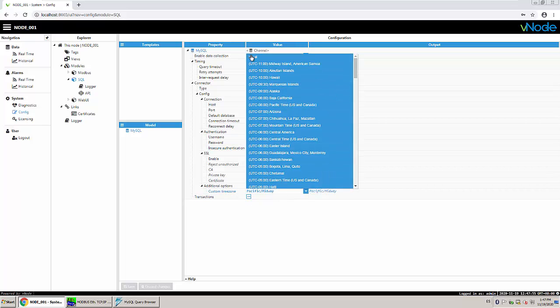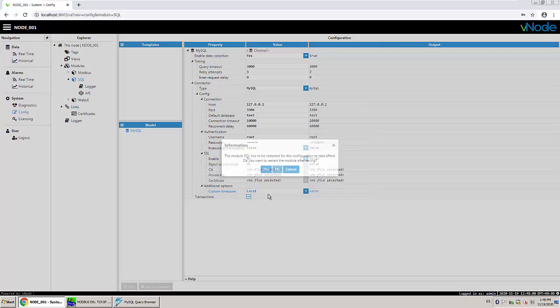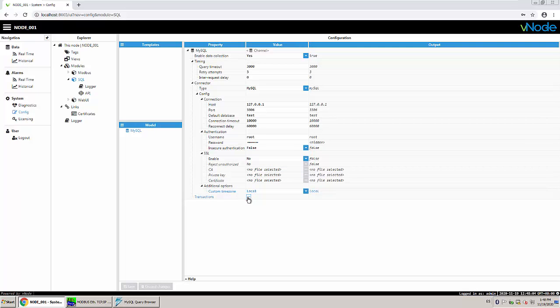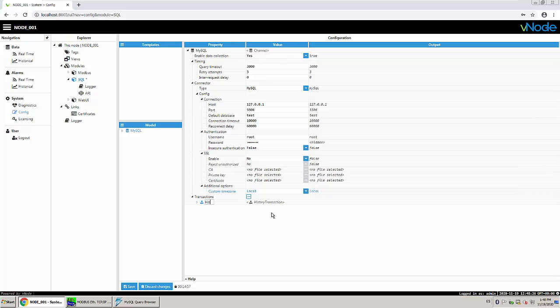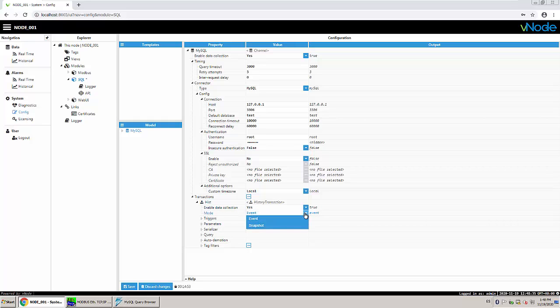Now that we're connected to the database, I'll change the time zone to local timestamp. Next I'm going to create transactions. Each transaction is a group of tags from vnode sent to a database table. You can create as many transactions as you want. I'm going to create a history transaction — I enable it and set it to send based on tag events, so only changes are sent to the database. If a tag value doesn't change, nothing is sent.